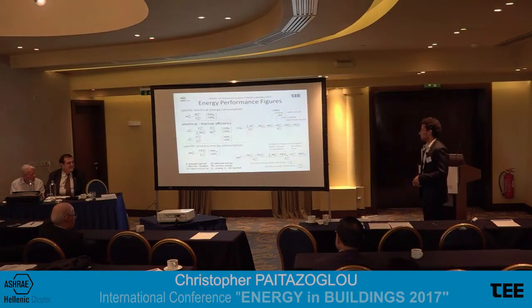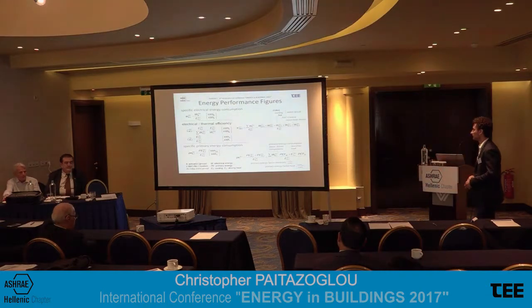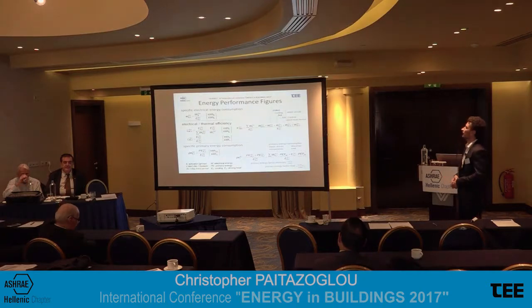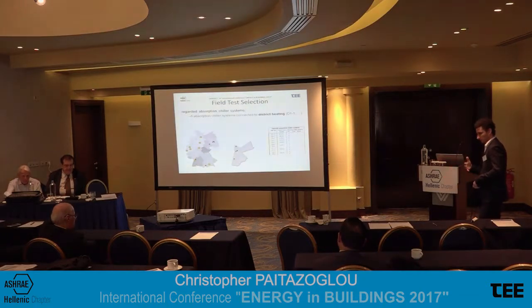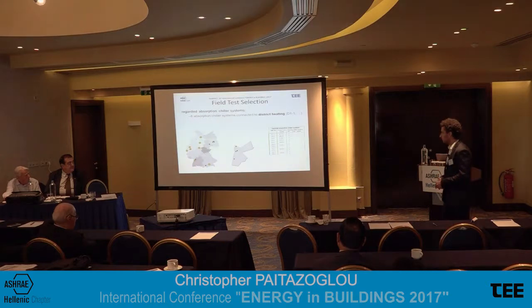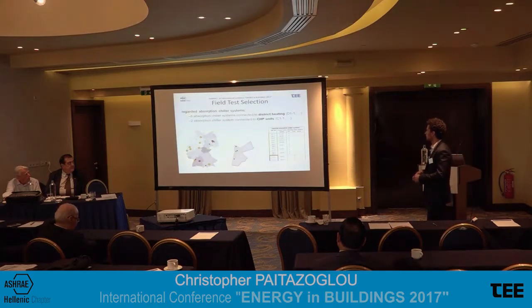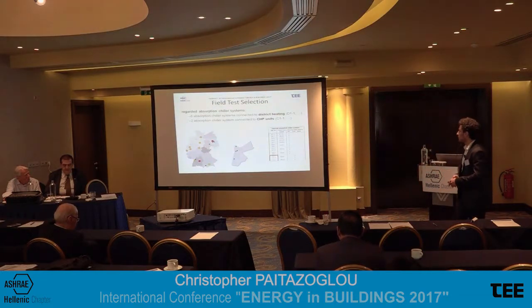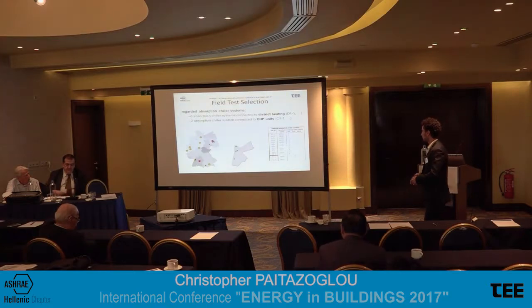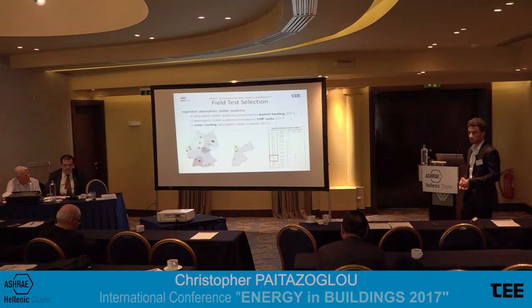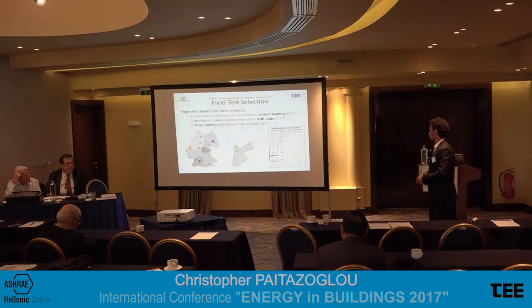The energy performance figures, which you probably know, are introduced in the paper, so I will not be going into detail. Keep in mind there's a difference between electrical and thermal efficiency. And let's get over to the evaluated sites in the paper. So we're talking about 8 absorption chillers connected to district heating. They are called D1 to D8. Then 3 systems or 2 systems with 3 chillers concerning CHP systems. They are called C1 to C2. And last of all, 3 solar cooling systems, they are called S1 to S3.